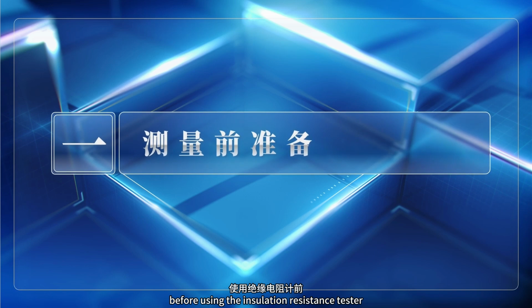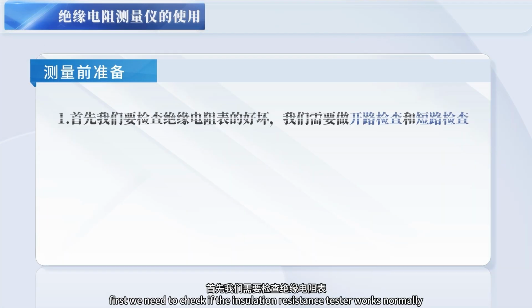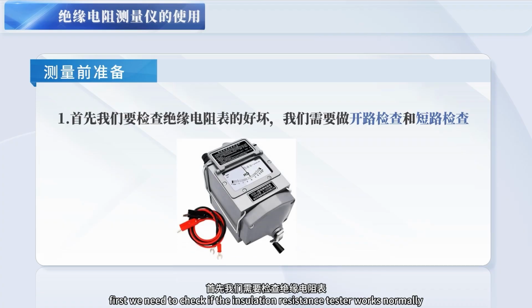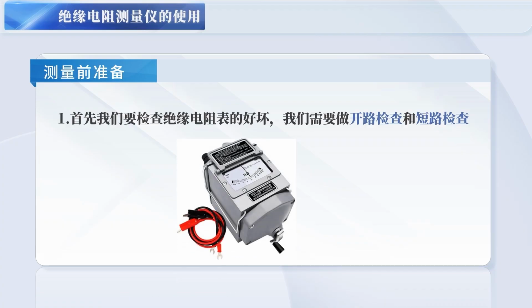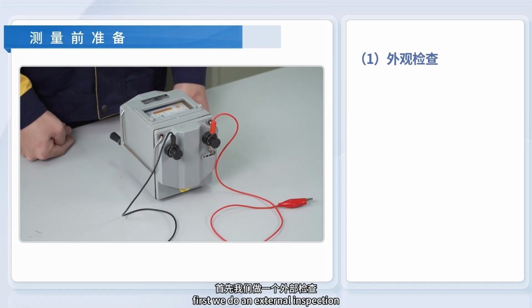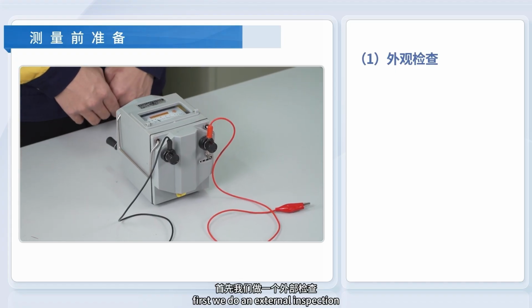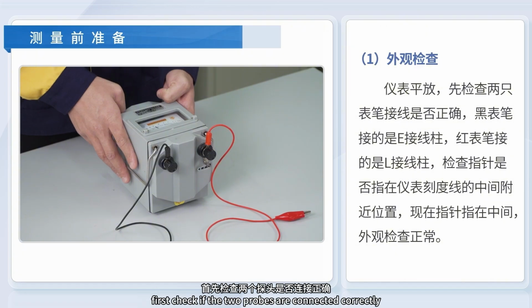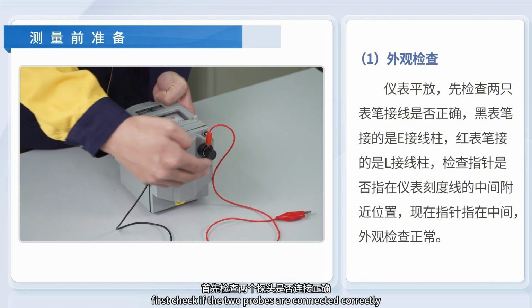Before using the insulation resistance tester, we need to make the following checks. First, we need to check if the insulation resistance tester works normally. We need to do an open circuit check and short circuit check. First, we do an external inspection. Place the instrument flat. First, check if the two probes are connected correctly.